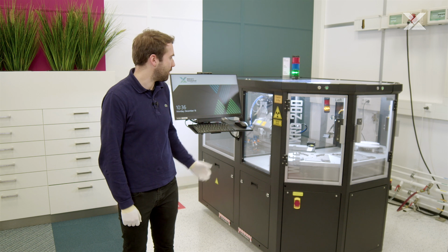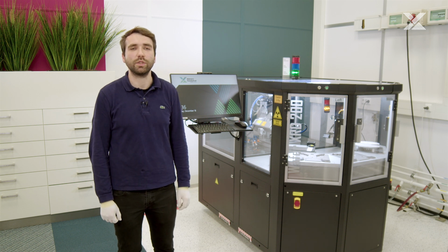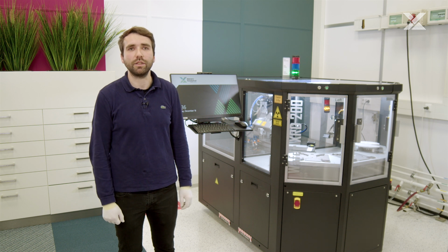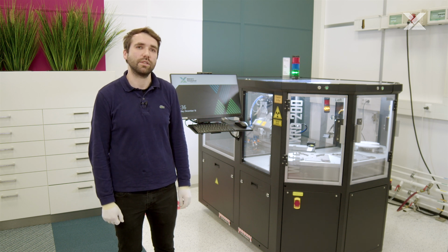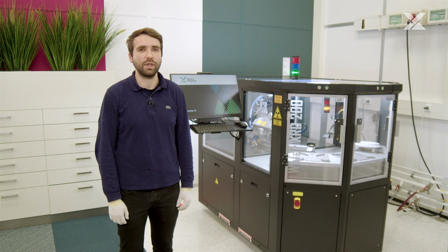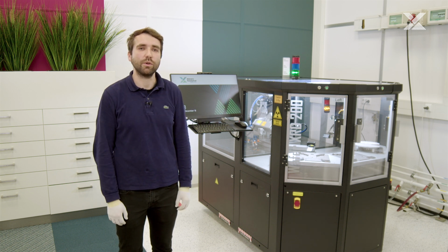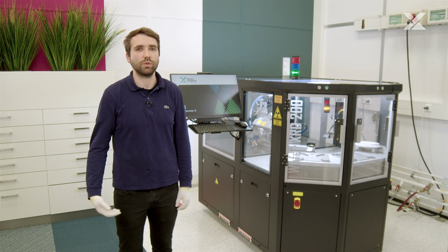For example, for wafers containing flats, the two most important feature parameters are the flat width and the flat depth. Such features can be measured with very, very high precision. We're talking about standard deviations of thousandths and ten-thousandths of a millimeter. Taking into account the high throughput of the system and that the system is measuring hundreds of thousands of wafers, it's really important to identify every single wafer during the process of measurement.